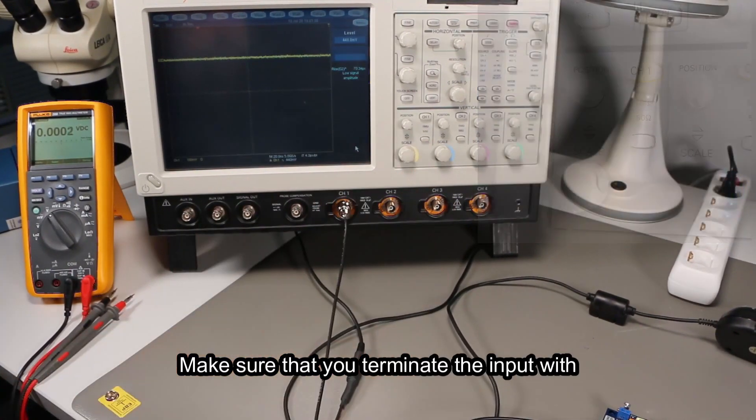Make sure that you terminate the input with 50 ohms, otherwise the signals are disturbed.